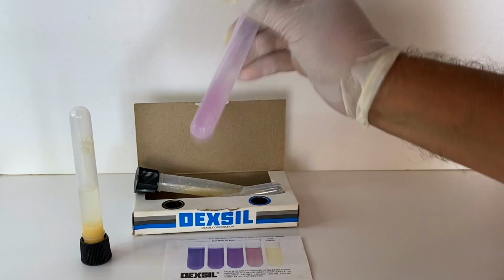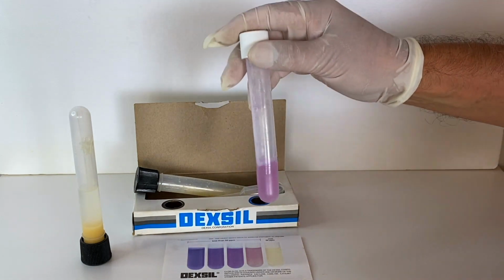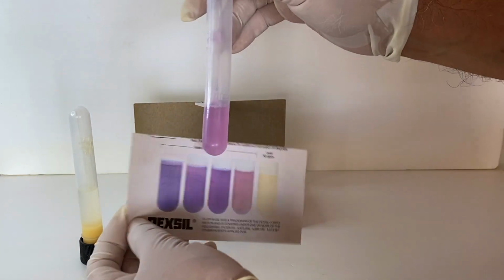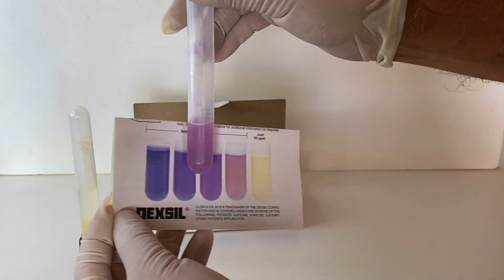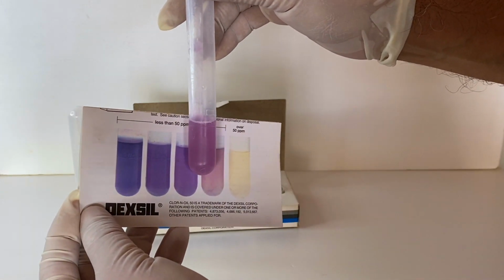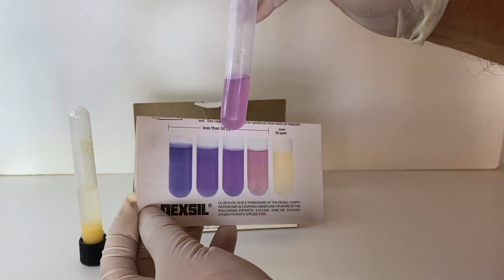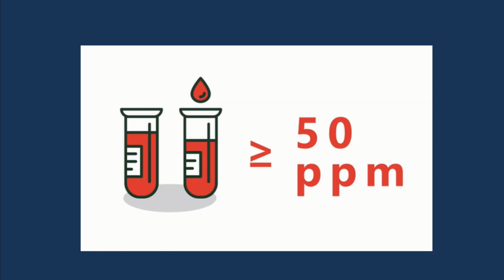The PCB level is determined by a color test. When the sample in the test turns blue or purple, you can be assured your oil sample is below the action level of 50 parts per million. When the color is yellow or colorless, it is above. Samples that have concentrations equal to or higher than 50 parts per million of PCB are labeled positive from the screening.